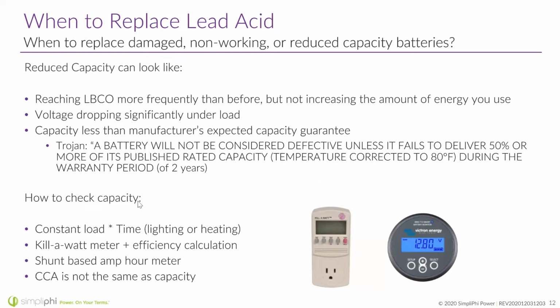So here is how to check the capacity of your battery. Number one, you can kind of estimate it manually by using a constant known load of lighting. Maybe you've got 10 100-watt light bulbs, and that equals 1,000 watts. And maybe you use that for 2 hours. So 1,000 watts for 2 hours is 2 kilowatt hours. So that's a simple calculation right there. But you'd also need to factor in some efficiency of your inverter and wire losses there.